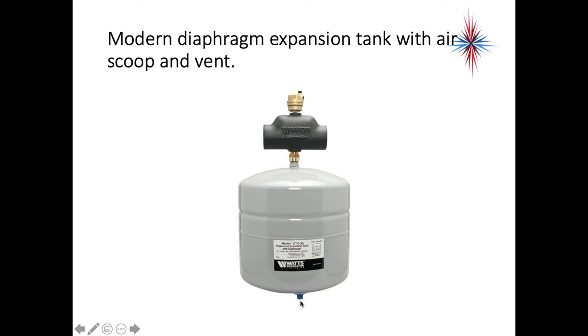There is a Schrader valve at the bottom of the expansion tank so that we can adjust the pressure. The air scoop is very simple — water flows through in the direction of the arrow, and air gets pulled out of the water and sent out through the automatic air bleed at the top.